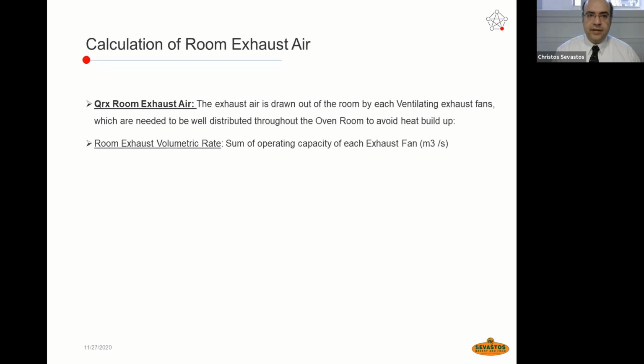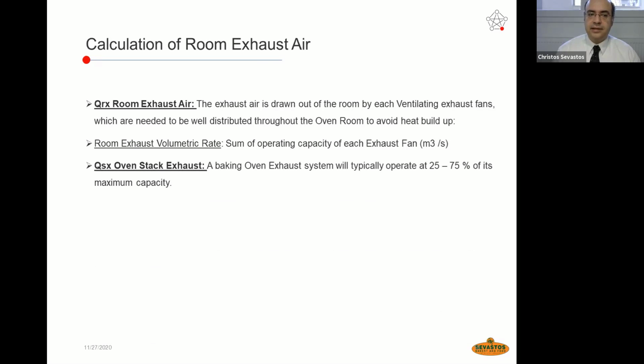The other factor is to calculate the room exhaust air, QRX. The exhaust air is drawn out of the room by ventilating exhaust fans, which need to be well distributed throughout the oven room to avoid heat buildup. This factor is going to give us the number of fans needed in order to apply a steady airflow, covering the demands of the oven and also the necessity of extracting the heat. Room exhaust volumetric rate is the sum of the operating capacity of each exhaust fan. This factor gives us how many powered exhaust fans we need to apply in this room where we are going to have tunnel ovens.